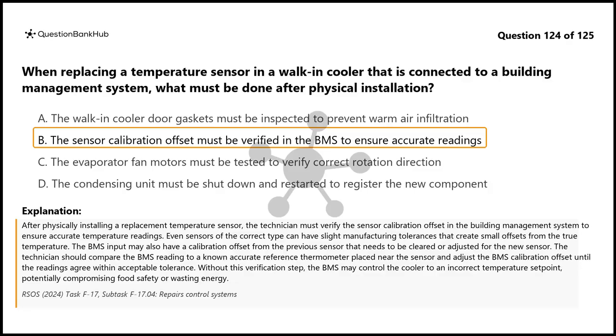for the new sensor. The technician should compare the BMS reading to a known accurate reference thermometer placed near the sensor and adjust the BMS calibration offset until the readings agree within an acceptable tolerance. Without this verification step, the BMS may control the cooler to an incorrect temperature setpoint, potentially compromising food safety or wasting energy.